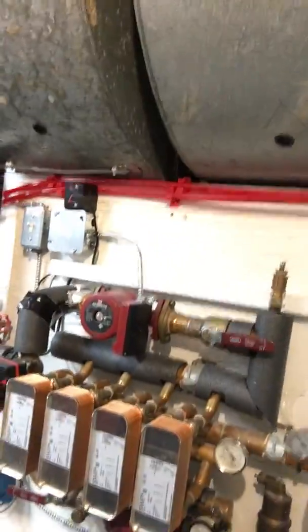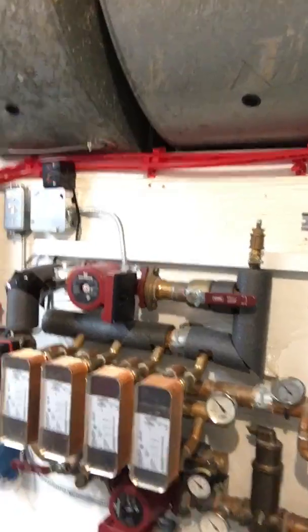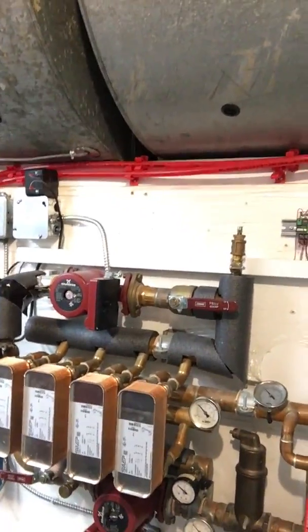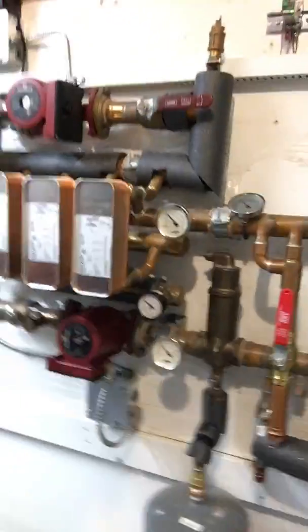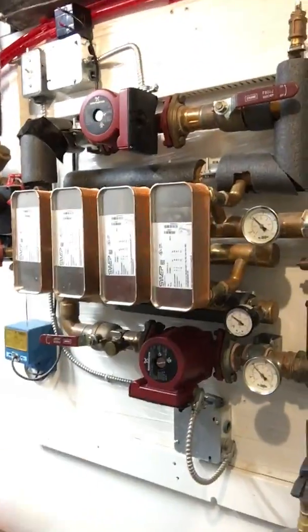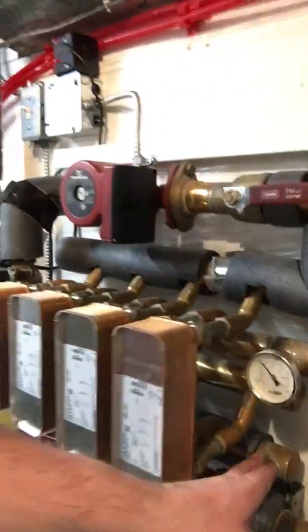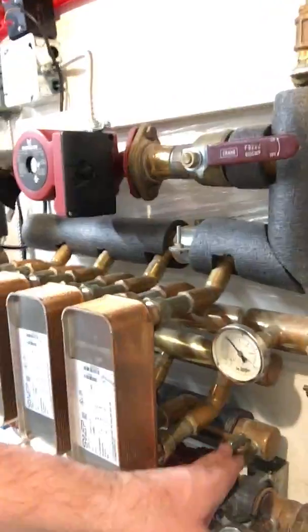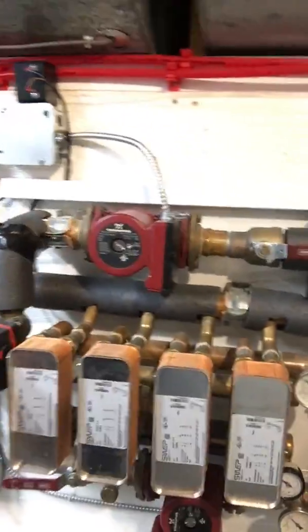So we have a snow ice melting system here, and we have about 1,400 square feet of driveway and walkway that does the snow ice melting. This is all the glycol system down over here on this side. There's our circulator there, gauges. Hey, notice the isolation valves, service valves, and the pressure gauges. That's always nice to have. And this is on the boiler side. So this is the domestic, our glycol side. We've got a three-way diverting valve.